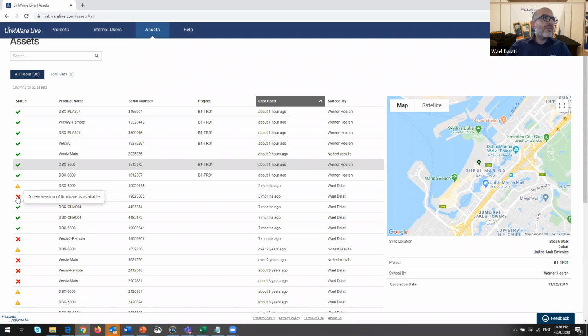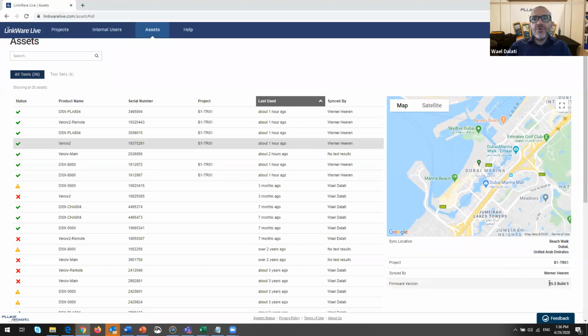The X means that the firmware version is wrong or could be a new version. Werner is using, as we saw earlier on the Versiv, firmware version 6.5, which is the correct one that we're using now. But if I look at this machine, it's using version 6.1 build 3. So I need to update my firmware on this one. This is a way to see things in an interesting way.